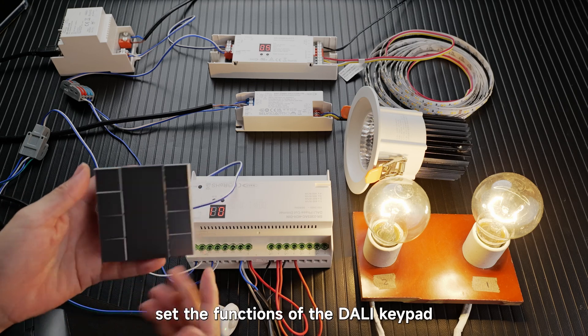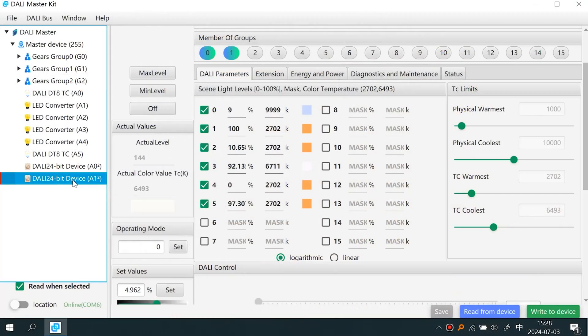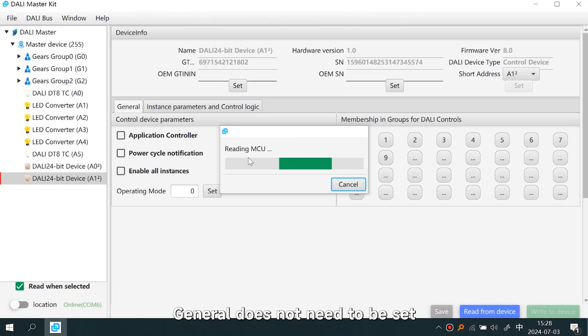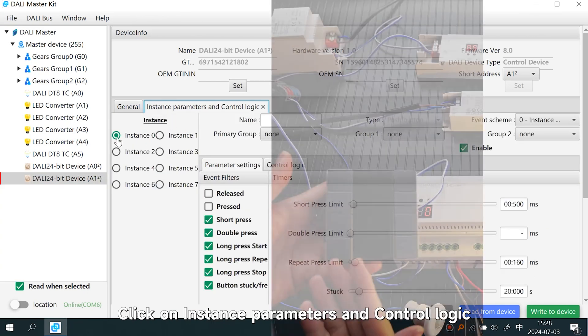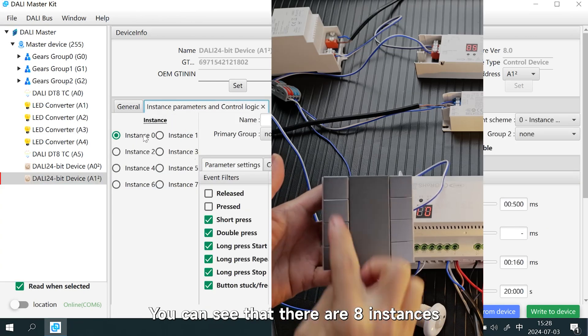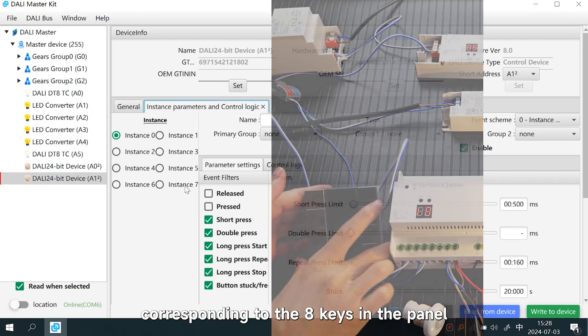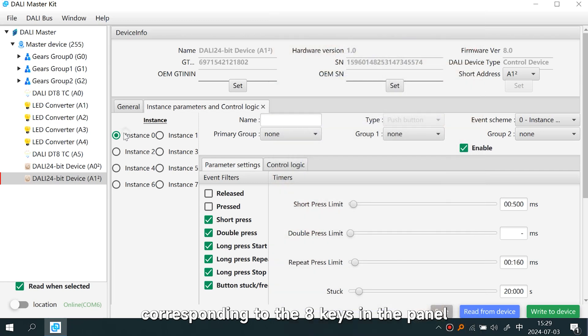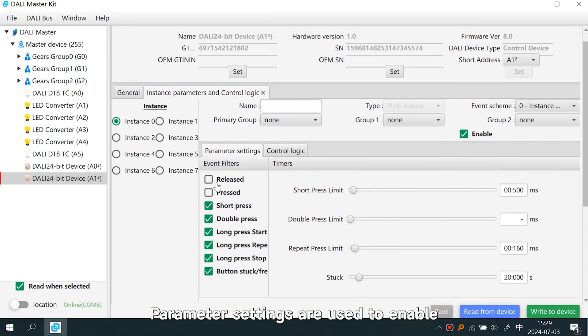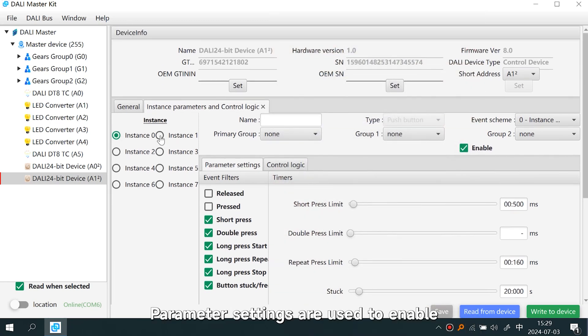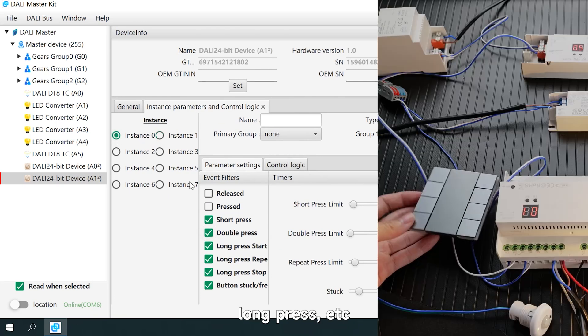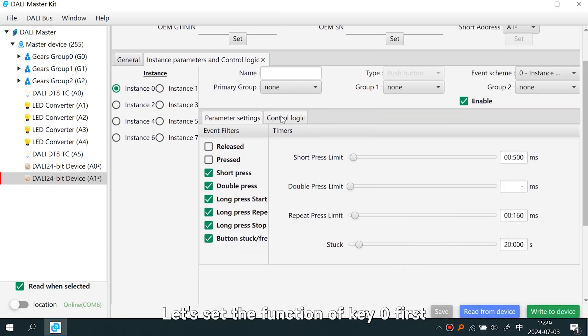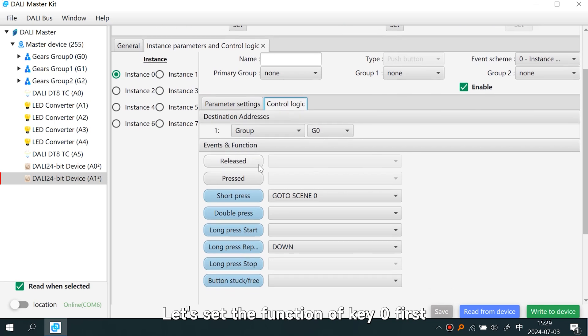Next, set the functions of the DALI keypad. General settings do not need to be changed. Click on Instance Parameters and Control Logic — you can see there are eight instances corresponding to the eight keys on the panel. Parameter settings are used to enable or disable key actions such as click, double click, and long press. Let's set the function of Key Zero first.